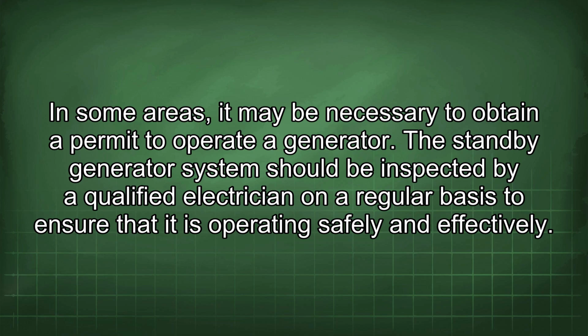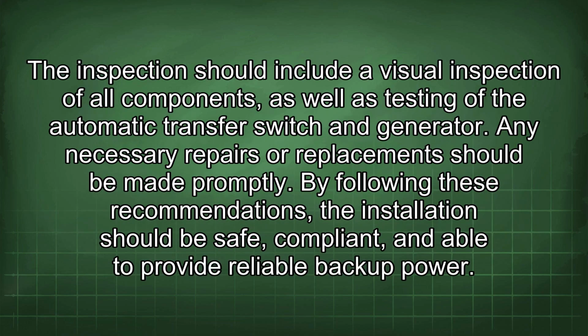The standby generator system should be inspected by a qualified electrician on a regular basis to ensure that it is operating safely and effectively. The inspection should include a visual inspection of all components, as well as testing of the automatic transfer switch and generator. Any necessary repairs or replacements should be made promptly. By following these recommendations, the installation should be safe, compliant, and able to provide reliable backup power.